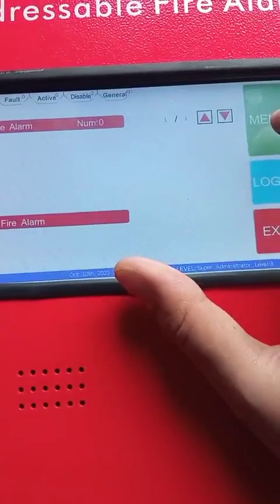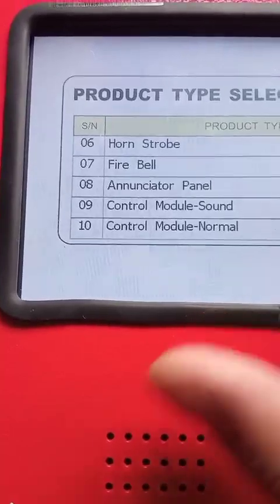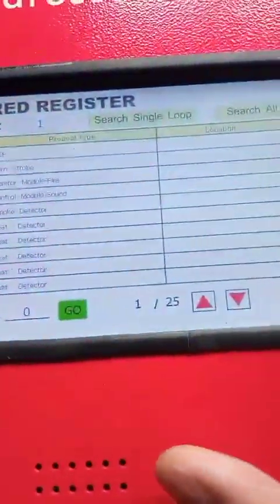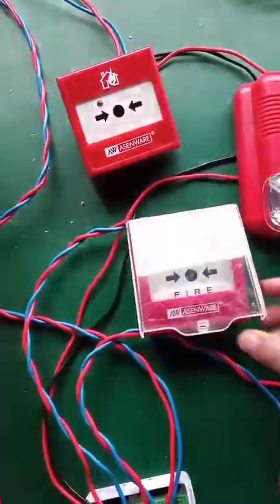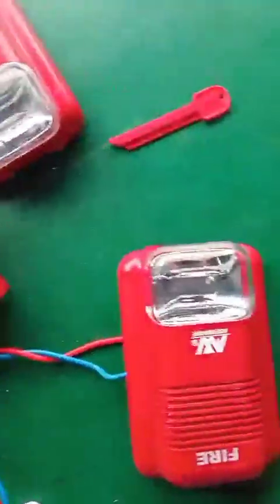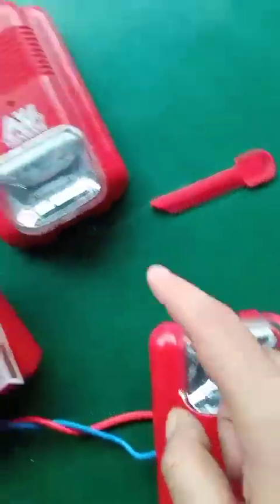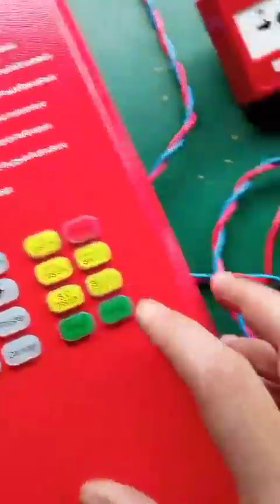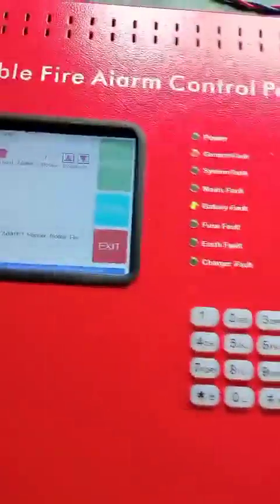Now I will choose control module sound mode so you will see that the silence button will work. I choose control module sound and press confirm. Now when I press the MCP and then press the silence button, the sounder stops. This is because with control module sound mode, pressing the silence button stops the sounder connected to this module. If I use control module normal mode, pressing the silence button has no effect on the sounder connected to this module.